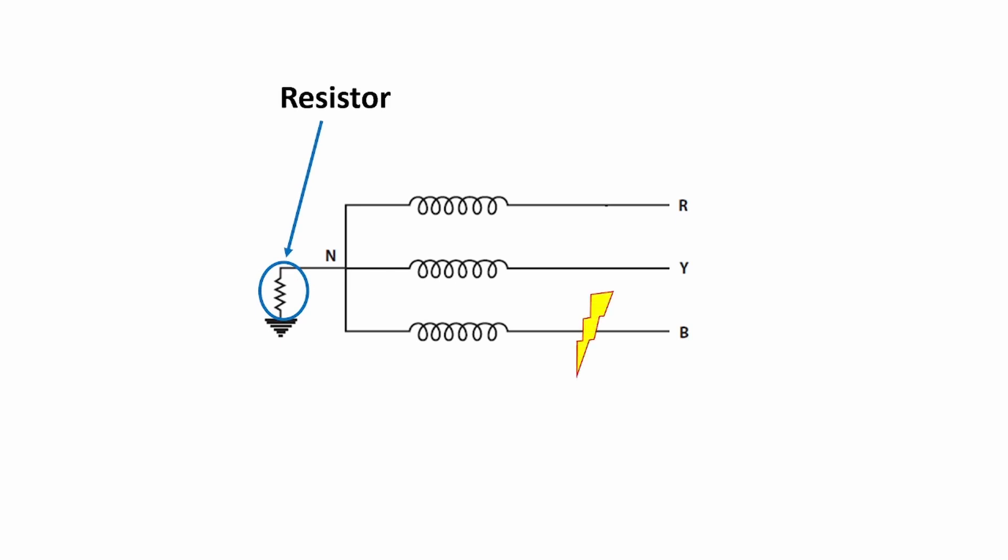Now let's discuss how NGR protects equipment. Suppose this is the equipment and its neutral is grounded with a resistor. When an earth fault occurs, fault current will flow from the fault point to ground point.